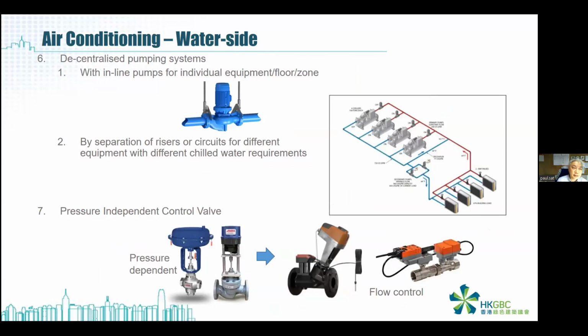And the next one is we use the inline pump. As you know, in conventional air conditioning flow control, mostly they use control valves, but there are so many problems in using the control valve. One is they will create a very large resistance when the flow rate requirement is very low. So people may talk about using some discharge pump or this inline pump for specific zoning or equipment.